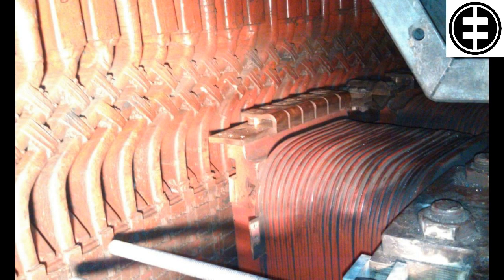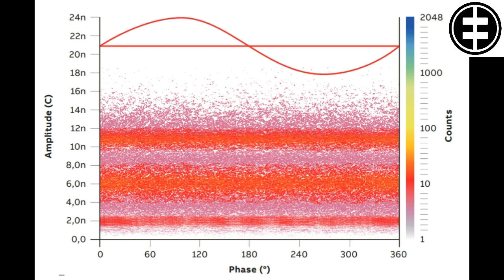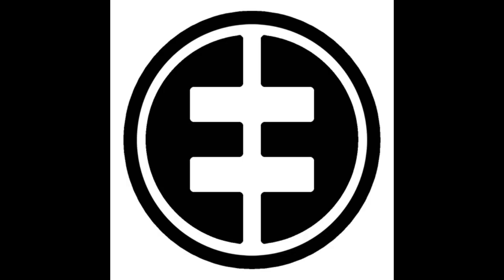There is also no direct correlation between PD magnitude and insulation lifetime because, for a given motor or generator, electrical stress may not be the dominant factor behind insulation aging. Furthermore, it is fairly meaningless to state that PD is low; absolute PD magnitudes are very difficult to evaluate, which is why trends in PD levels should be used instead.